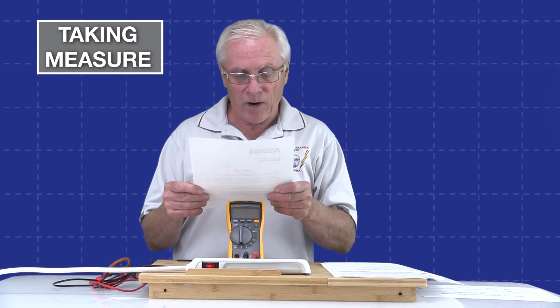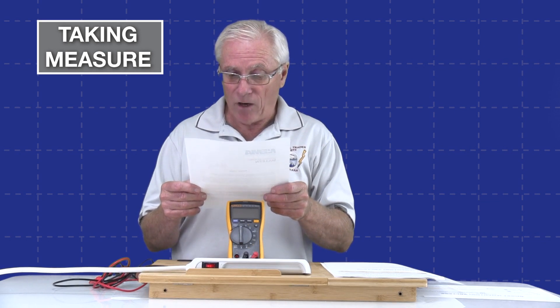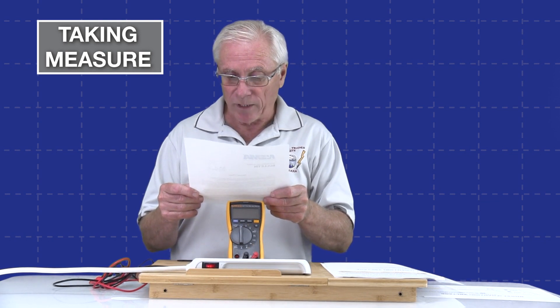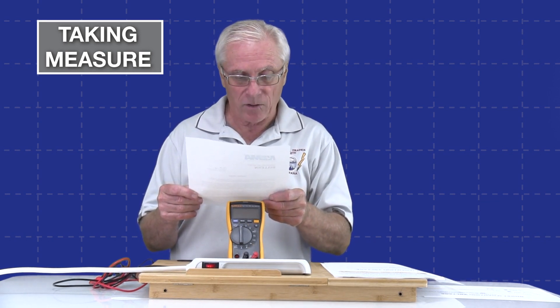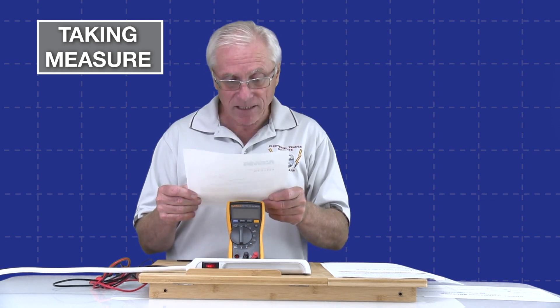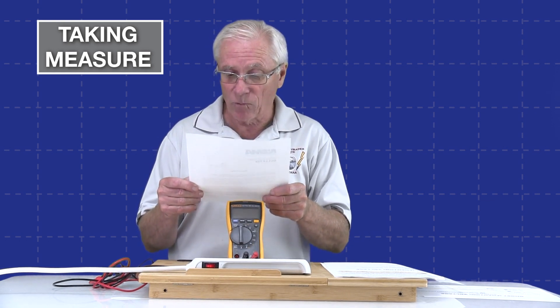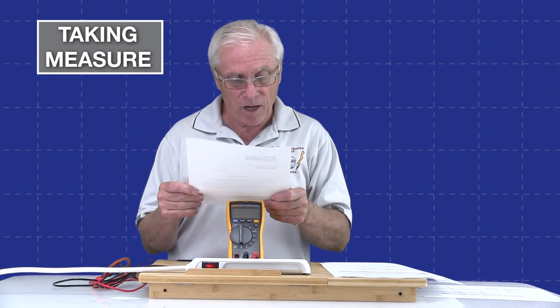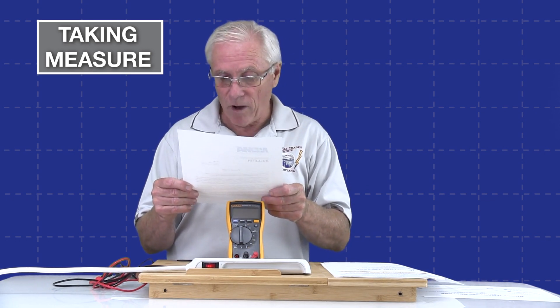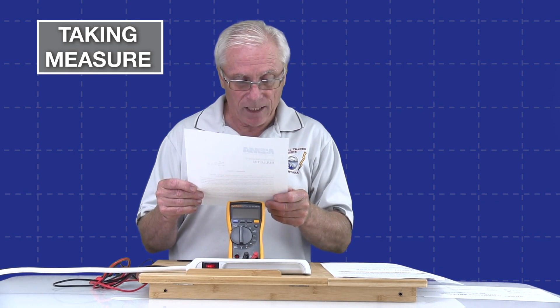According to Underwriters Laboratories Inc., this can be a harmless reading and can be caused by the high impedance inputs of the measuring instrument, which places very little loading on the circuit under test. The capacitance is increased as the length of the run is increased. A 50-foot run may produce a pronounced capacitance effect, whereas a one-foot sample may not produce any.